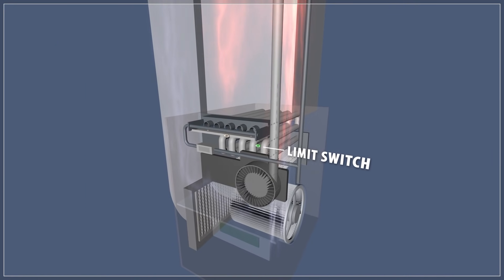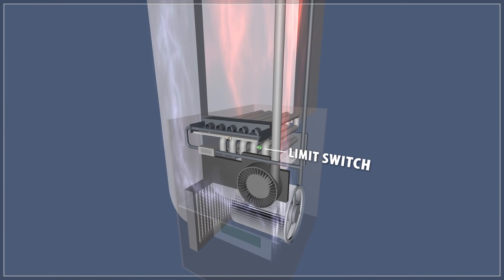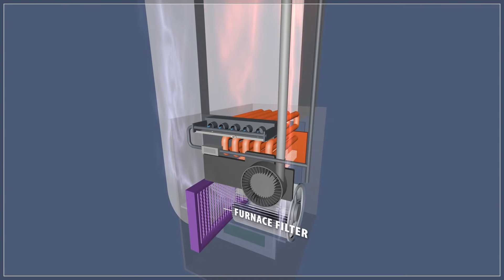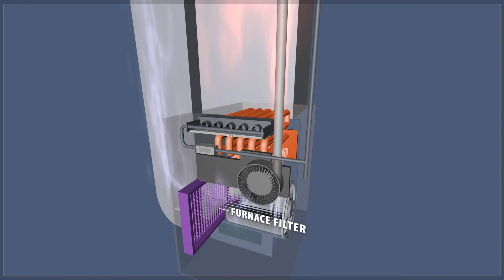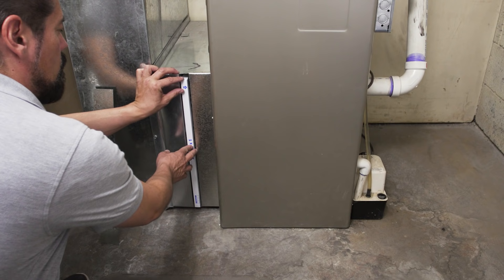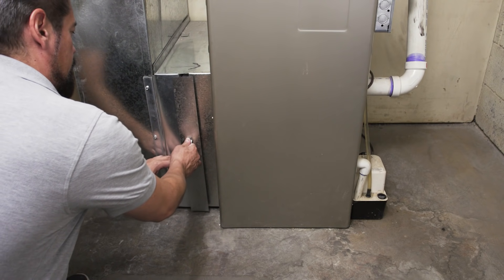The limit switch monitors the temperature of the air passing over the heat exchanger and will shut off the furnace if the system overheats. Any restriction of the airflow might cause the heat exchanger to overheat. This is why it's essential to replace the furnace filter every three to six months.